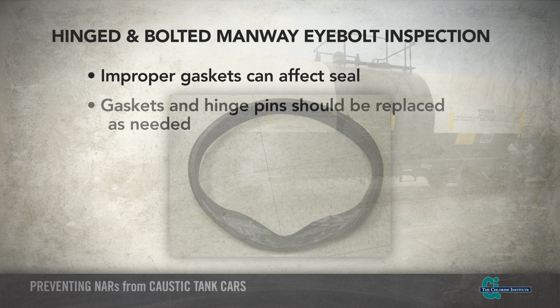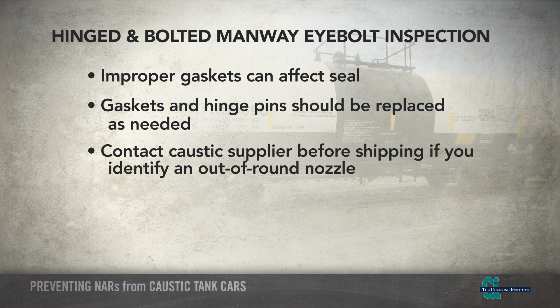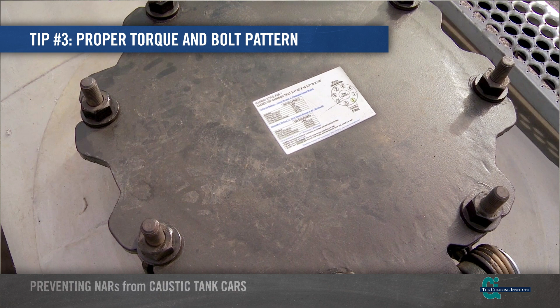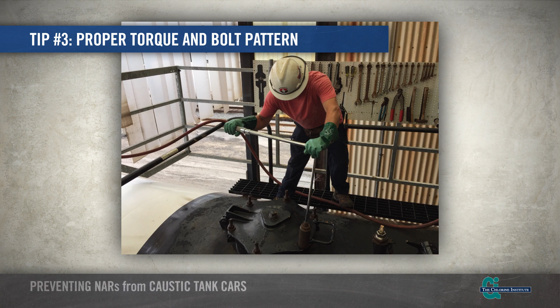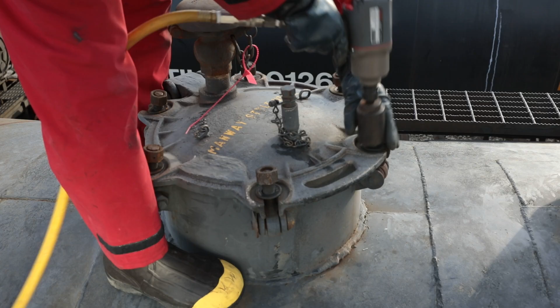Gaskets and hinge pins should be replaced as needed, per the caustic supplier company's tank car quality assurance program. Also, contact your supplier if you identify an out-of-round nozzle before shipping the car. Once all the hinged and bolted manway eye bolts and gasket are in good condition and in alignment, tighten all eye bolt nuts by hand until they are flush with the manway cover. Then all eye bolts should be tightened using the crisscross or star pattern torquing method using a proper tool.